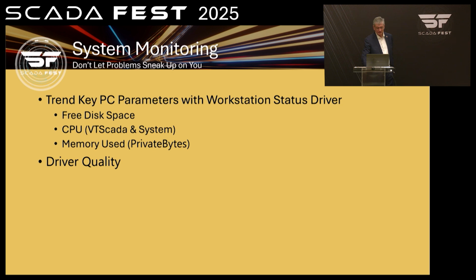But if you don't notice it, the retries on the driver will recover from that. They'll heal it. So I do two retries on my system and it keeps going, but it's getting worse and worse and worse, and I just don't see it until it starts to fail. So if you watch the driver quality, you can put an alarm on it. If this thing goes below 95%, 98%, whatever your quality level is, then you can say, an alarm: I'm still getting data, but the tree is growing taller.